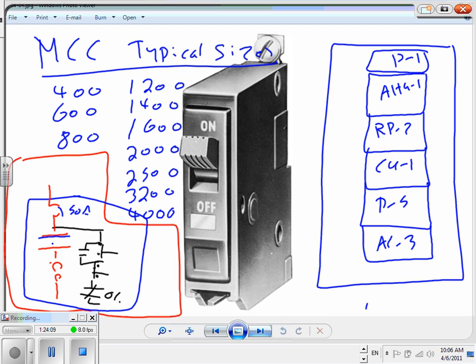So you can draw this MCC out, take it, put it on the table, and mechanically fix it, change the contacts in it. And while you're changing it, you don't want the air handling unit to be off, so you have a spare one just sitting for this. You plug it in while you're changing the contactor, mostly the contactor, changing the overload, adjusting the contacts. So that's the advantage of an MCC.